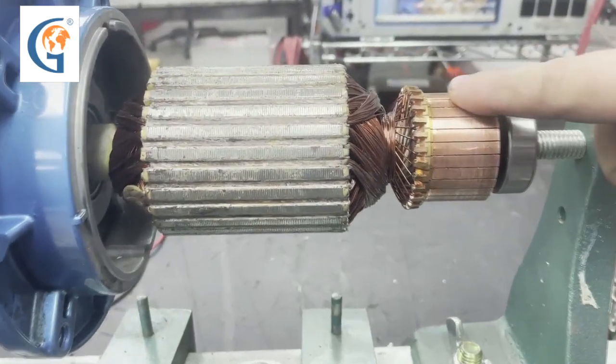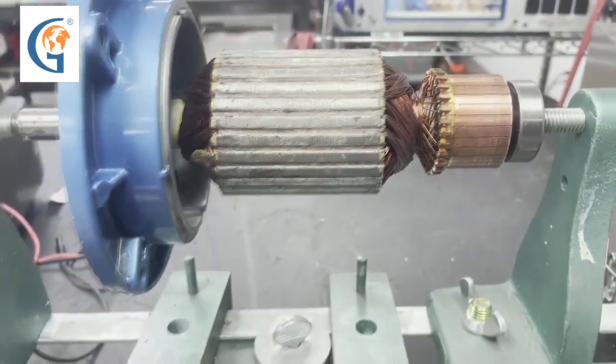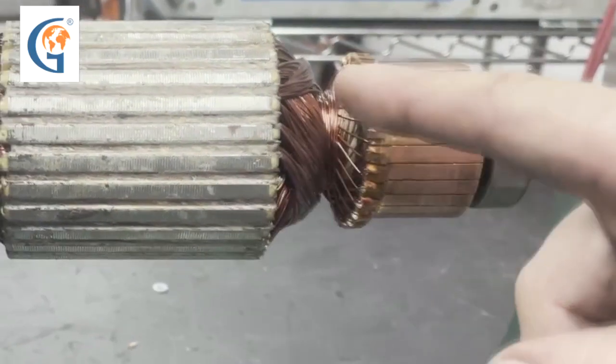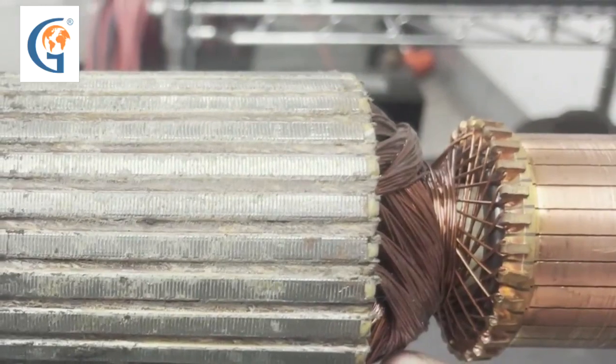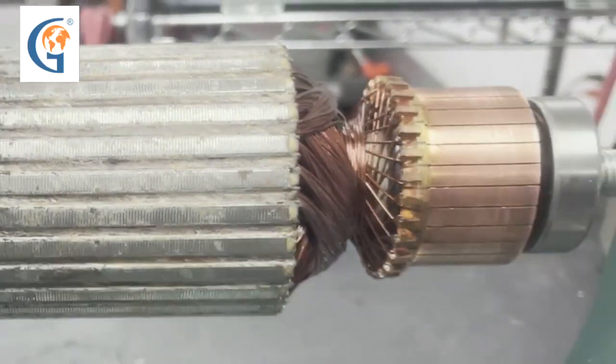And what we are going to be doing is a DC bar-to-bar test, so that we can determine if there are any turn-to-turn shorts in the windings of the armature. We'll be using one of our bar-to-bar testers here.